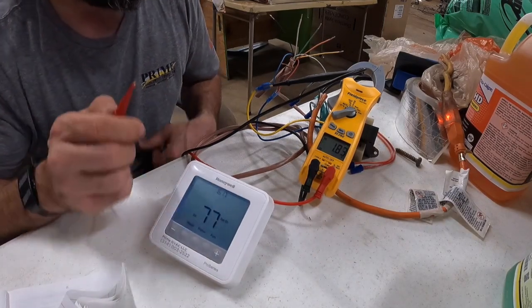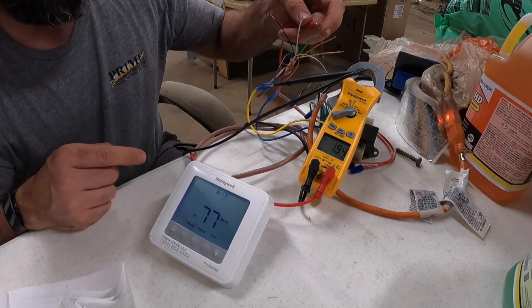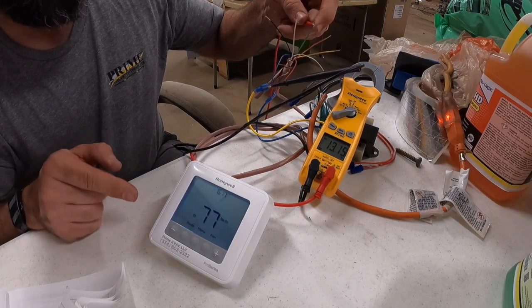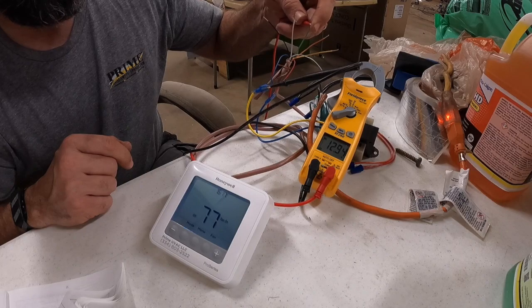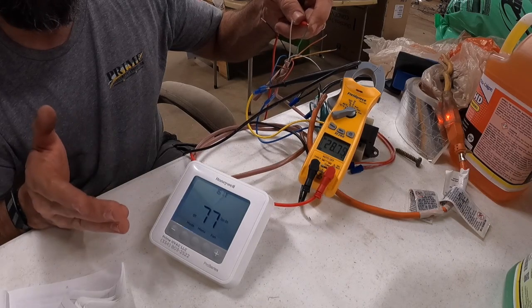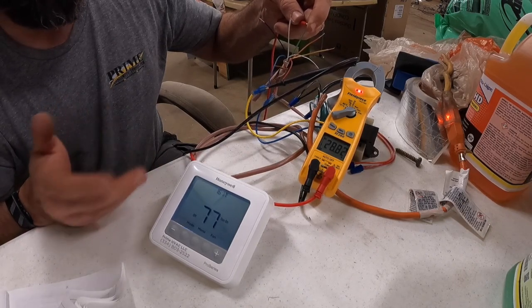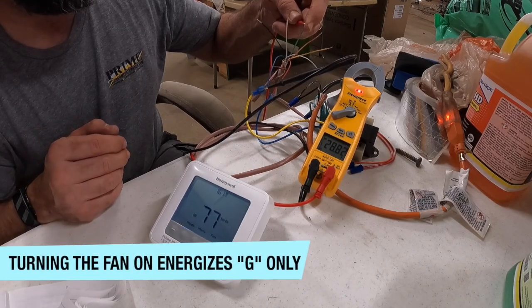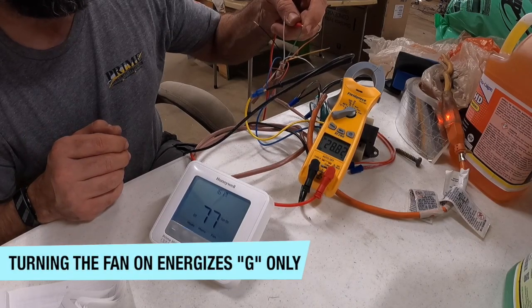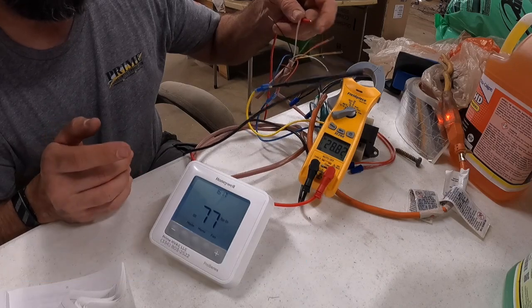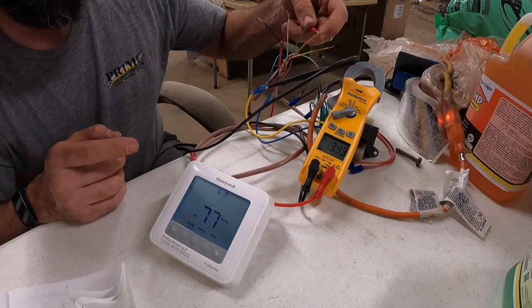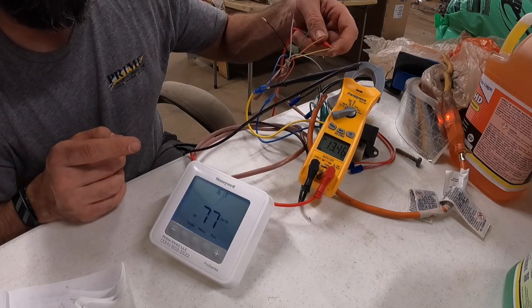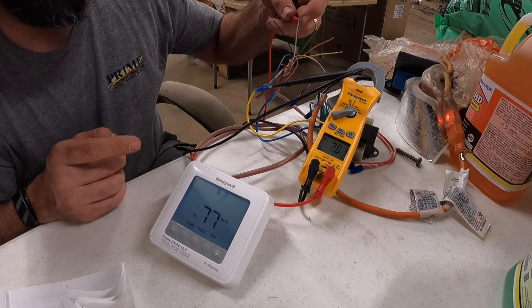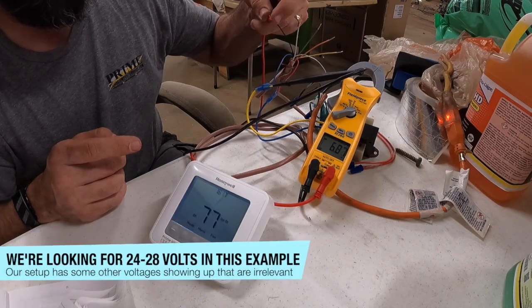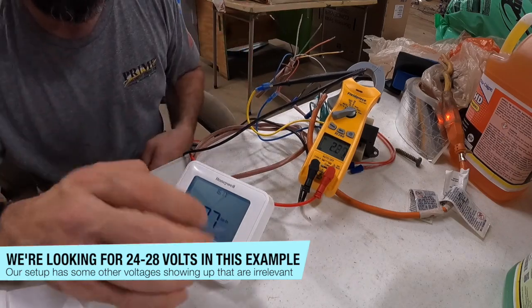It's going to click. It takes a minute. Now we're getting 28 volts, but it's over 24. As long as we're not getting up above 32, I think we're good. So we're sending that signal, and that's the G terminal in the thermostat. That's what the green wire was hooked up to, and it's not sending voltage on any other wire.